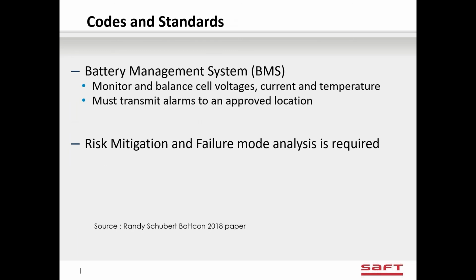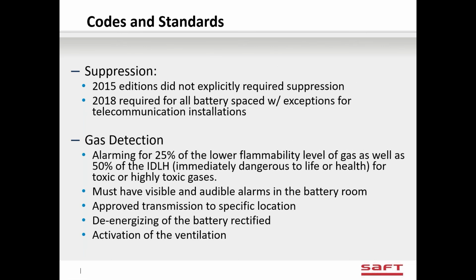Some other things, they require that the lithium-ion battery has a battery management system that monitors all the cells and has the ability to transmit the alarms to an approved location. They require that you do some risk and failure mode analysis for the room, and that considers your other things like fire suppression, gas detection. They want a risk analysis done of that whole room, like a DFMEA or a risk analysis. For gas detection, they want to alarm for 25% of the LFL, and they want that gas detection to activate ventilation so that you never get above the LFL levels.